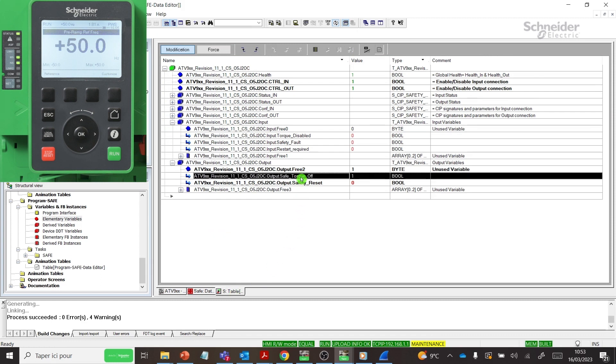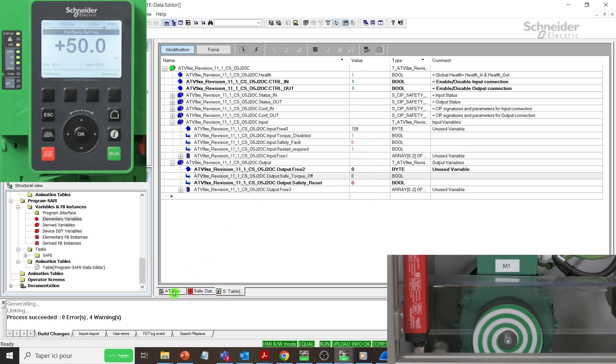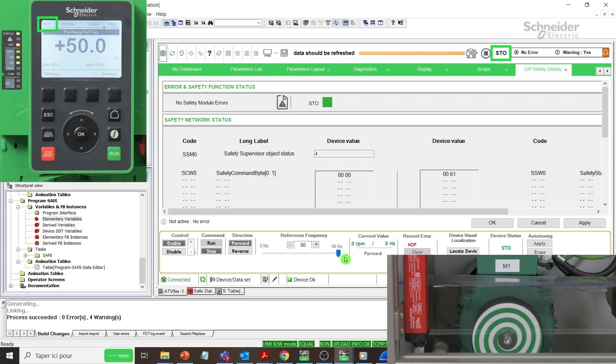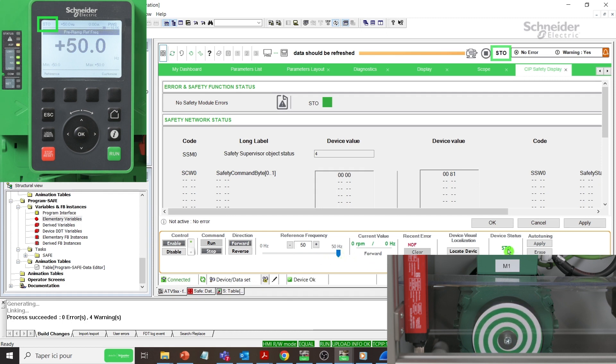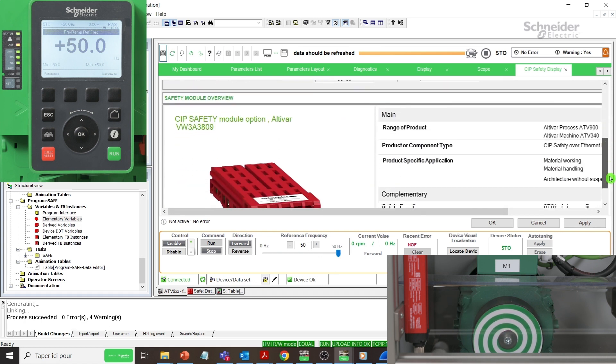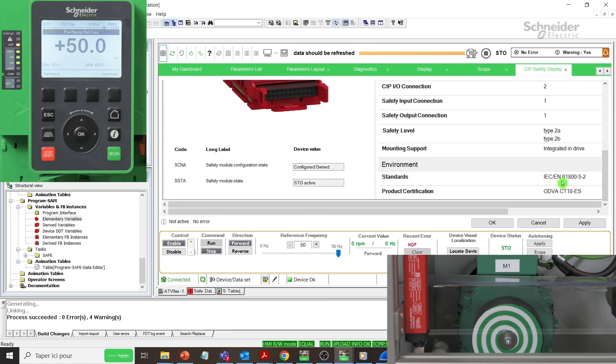Activate STO function by reset Output.Safe_Torque_Off to 0. See the Graphic Display Terminal HMIS state as STO state. ASF LED is yellow fixed and the motor stops in freewheel.